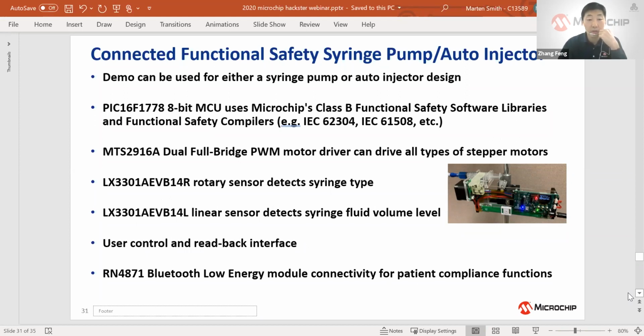To ensure the syringe pump operates as intended with safe shutdown if any exception or issue arises, this demo implemented a few functional safety routines, such as RAM memory integrity check, CPU register check, CPU program counter check, and flash memory CRC check.